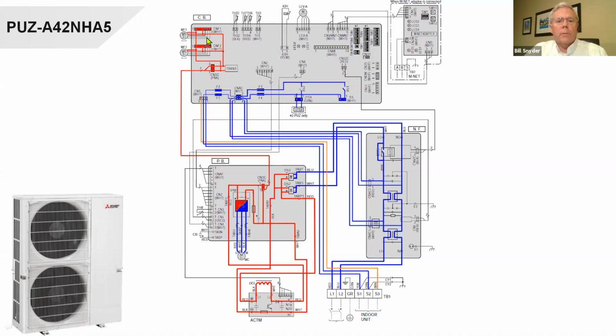These other wires coming back are telling the motor what to do and giving us feedback of what the motor is actually doing. Also on this board, there's a linear expansion valve, and some thermistors up here. And down here is the reversing valve, because this is a heat pump. It's a PUZ heat pump. If this was not a Z, if it was a PUY, this would not be used. That's why it says for PUZ only.